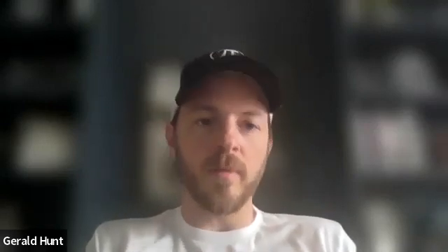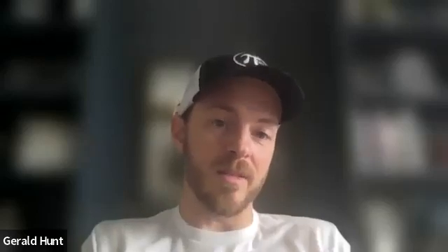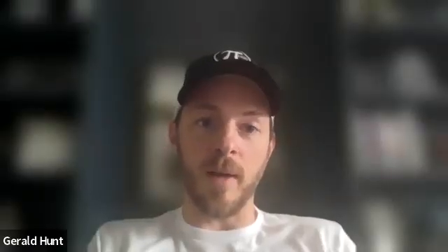Hey, Chad, real quick to add on to your comment about relative humidity. Over the years, folks I've talked to that don't necessarily understand all the chemistry associated with that, the mentality is just cooler is better. But in terms of understanding the essence of relative humidity, that's not necessarily the case under all conditions, right? Correct. The temperature is essentially just a catalyst for what's happening there. So if you drop the temperature, you're going to slow down the inevitable, but unless you get the moisture out, it's still inevitable. Right. In the sense that moisture is fixed, but as temperature drops, you're actually bringing yourself closer to the dew point. Yep. No, that's a good distinction.